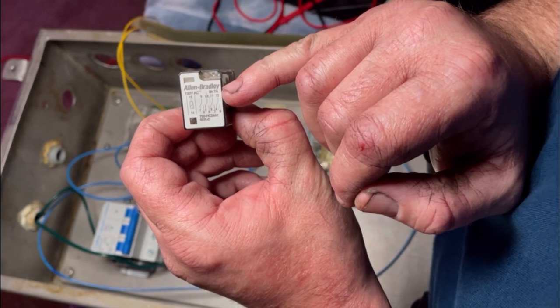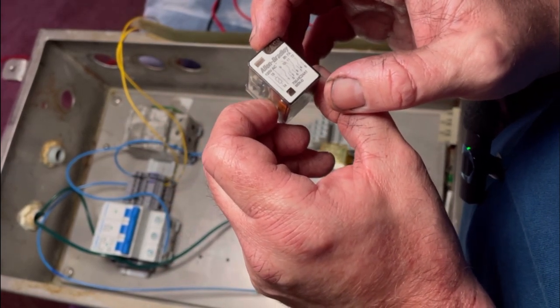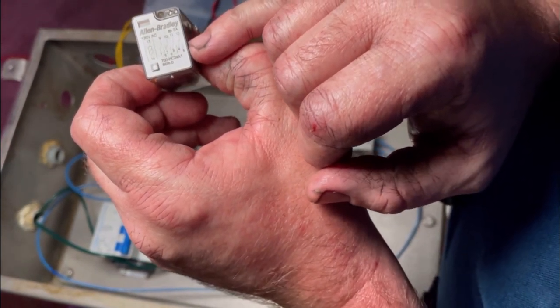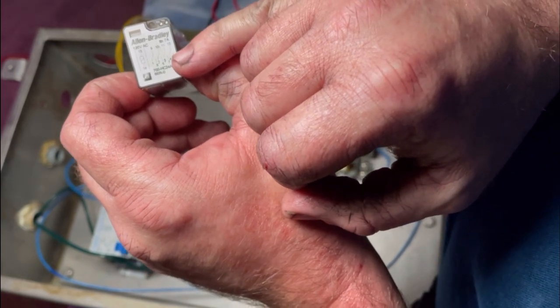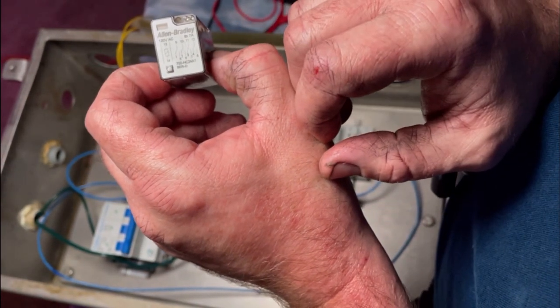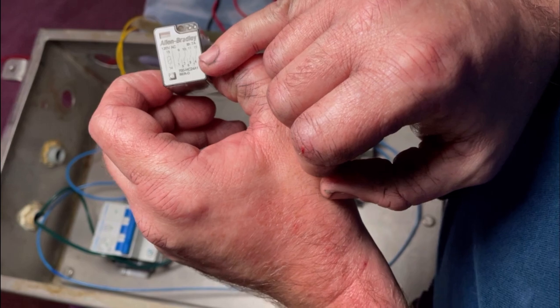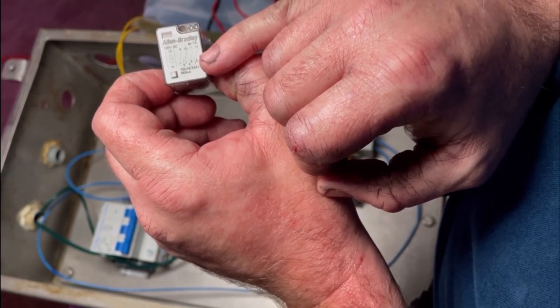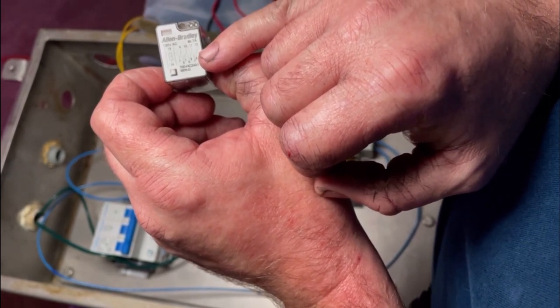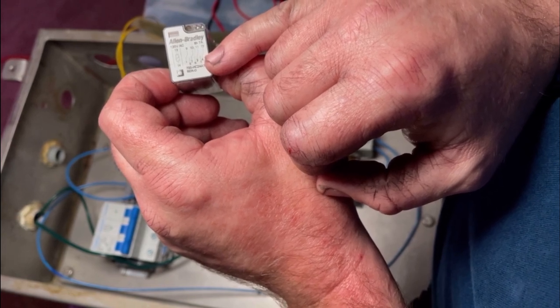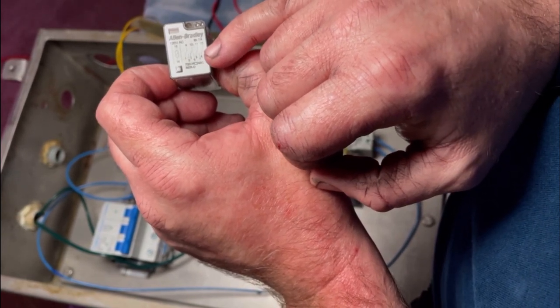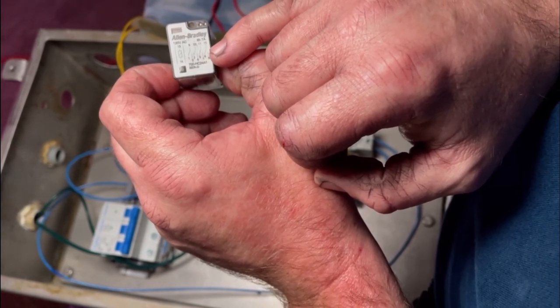And we want to go to the normally open. So we're going to go to terminal 8. Terminal 4 would be the normally closed point. So when you plug it in, it would be energized. And then when you energize, like terminal 4 would be energized without the relay on. And then when you turn the relay on, this little guy is going to go over that way.